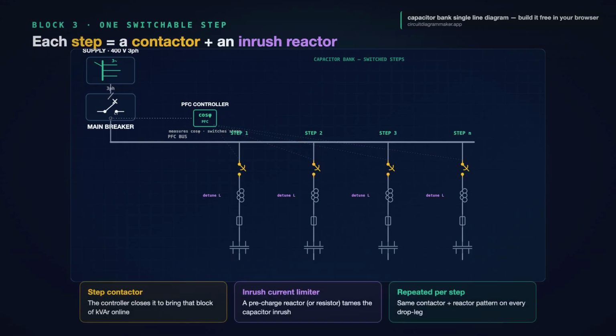Block 3, the heart of the bank, a single step, and every step is built the same way. At the top of the step is a contactor, the coil-driven switch the controller closes to bring that block of capacitance online. You will spot it by the little arc on the moving contact, just like a motor contactor. But there's a catch with capacitors. The instant you connect one, it pulls a huge inrush current, far more than its steady current. So directly below the contactor sits an inrush current limiter, a small pre-charge reactor, an inductor, or sometimes a resistor, that tames that switch-on surge so it does not weld the contacts or trip the breaker. Contactor, then reactor. The same pattern repeats on every step.